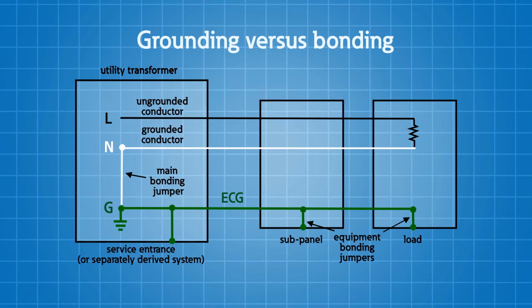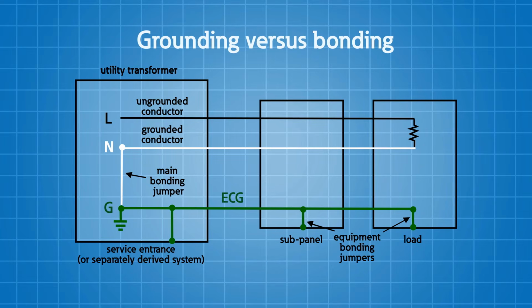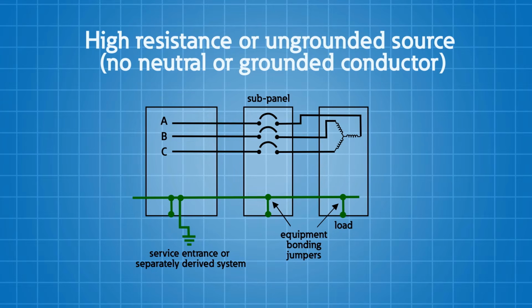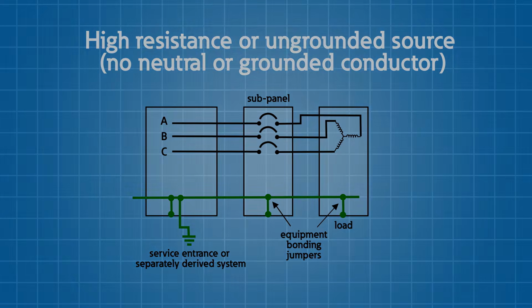Now, everything that we have just discussed around power system grounding is separate from the bonding discussion that we had, because regardless of the grounding method for the power distribution system, the equipment grounding doesn't change and bonding is still critical and required. The difference is that the grounded conductor and the grounding conductor must be insulated from each other outside of one point in the power distribution system where they're bonded. Any subpanel in a power system must not have a connection from the grounded conductor, which is typically the neutral, to ground. Remember too, this is only relevant if you have a grounded conductor, because with a delta high resistance system or an ungrounded system, you're not going to have that grounded conductor.